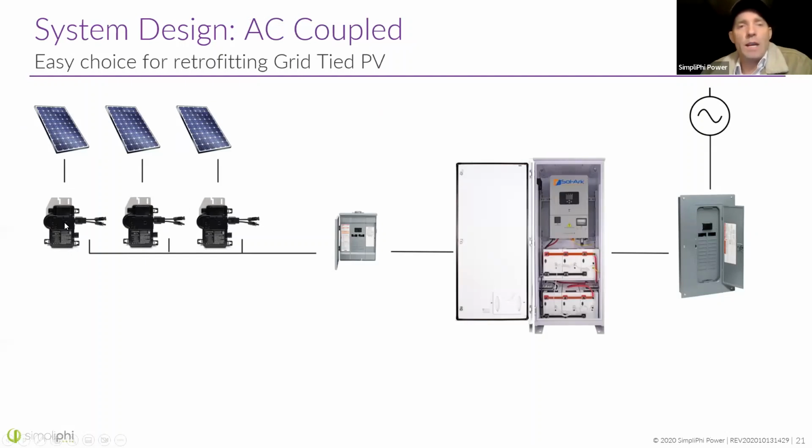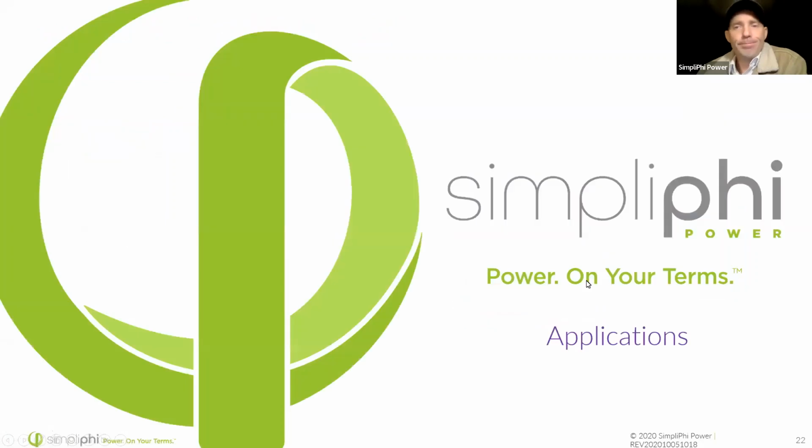The microinverters turn that to 240 volts AC. That is coming down to a separate disconnect box here. And so I've got this AC signal coming in. If I want to charge batteries, I have to have that second inverter. And that's what the Sol-Ark is doing here. I have a second inverter that allows that AC signal coming from the solar panels to be converted into DC to charge up the battery bank, the DC battery bank here.